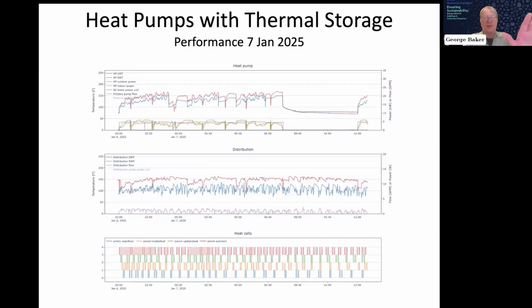So very quickly, this is a picture of what we're doing. I don't expect you to follow this except to see that we're collecting all kinds of data at very high resolution. This is the output of the heat pump, and when it's running, this is the output of the distribution system. You can see we're putting roughly 150-degree water into the house, coming back at about 130 degrees—about a 20-degree delta T in the heating system, just about what you'd like.